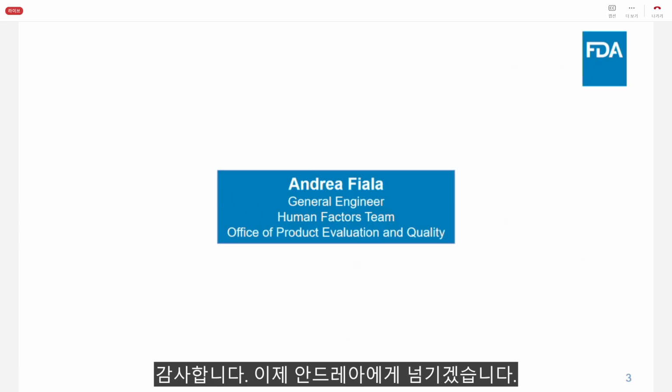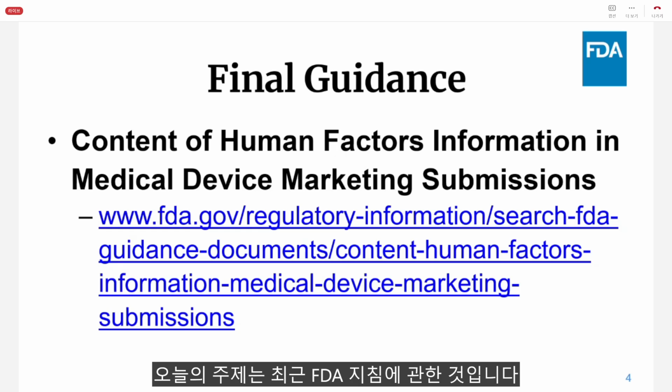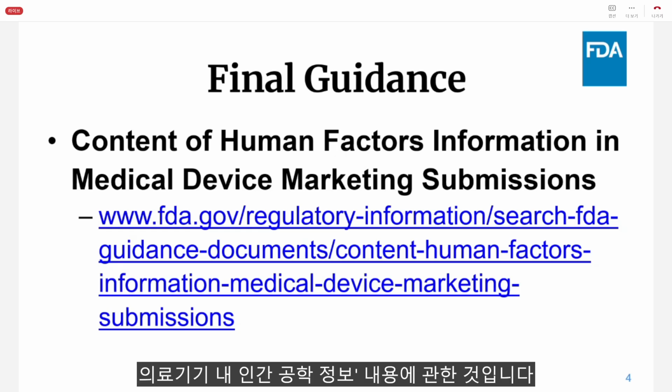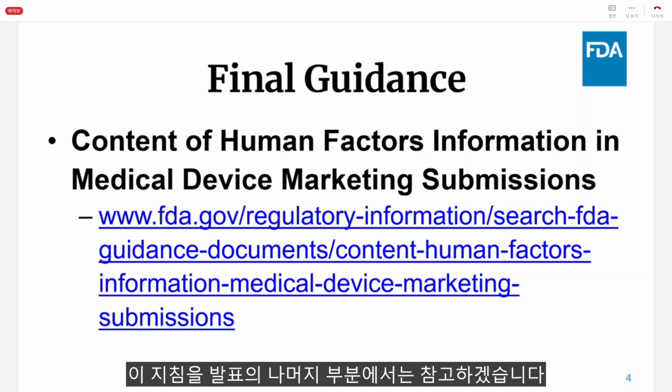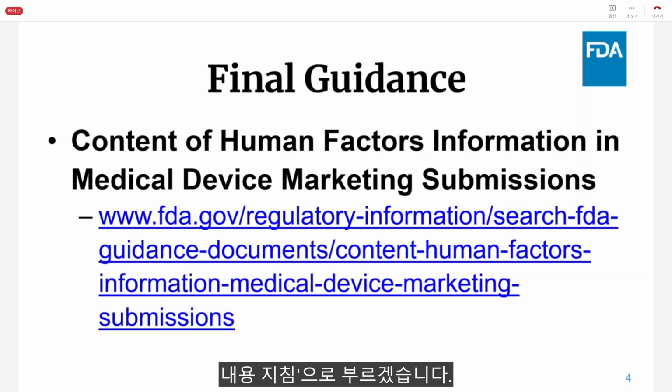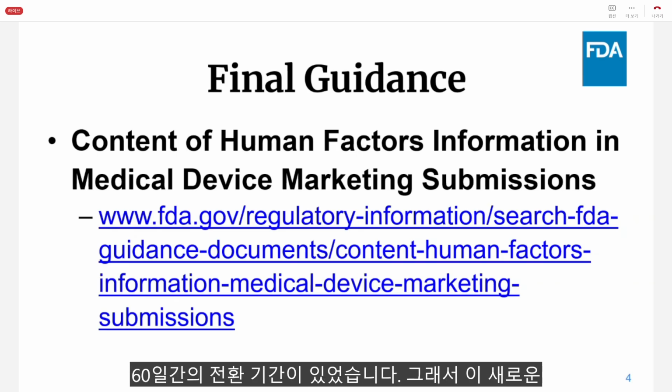Thank you, Kim. Welcome everyone, and thanks for joining us today. Today's topic will be about the recent FDA guidance titled Content of Human Factors Information in Medical Device Marketing Submissions. We will refer to this guidance for the remainder of the presentation as the Human Factors Content Guidance. Please note that this guidance was finalized on May 29, 2026, with a 60-day transition period, so this new guidance will be implemented on August 1, 2026.